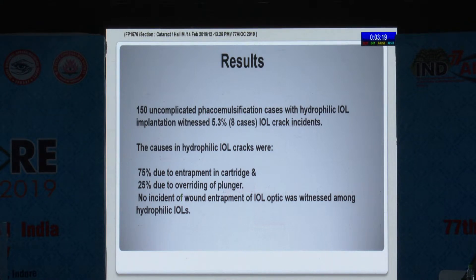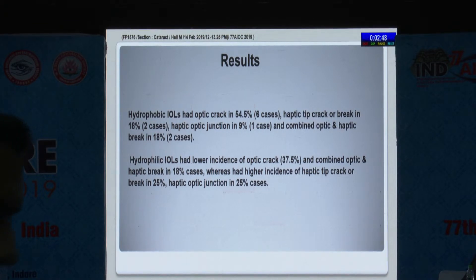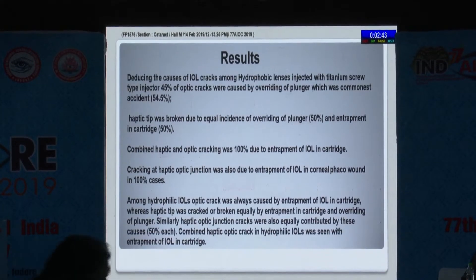No incidence of wound entrapment of IOL optic was witnessed among hydrophilic IOLs. Analyzing the crack types further, 54.5% of cases had an optic crack, one case had a haptic-optic junction break, and combined optic and haptic breaks were in 18%. For hydrophilic IOLs, more than one-third had an optic crack, combined optic and haptic break was in 18% of cases, and remaining cases had haptic junction involvement in 25%.